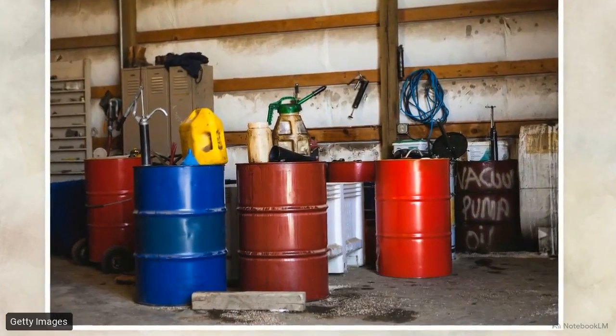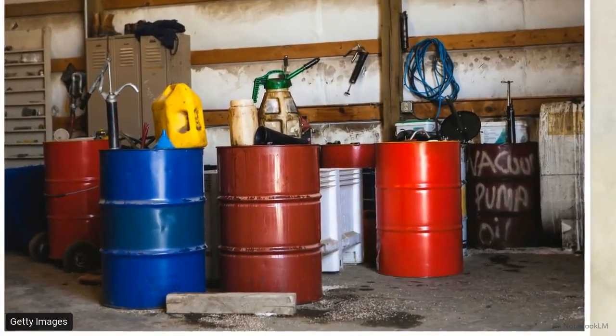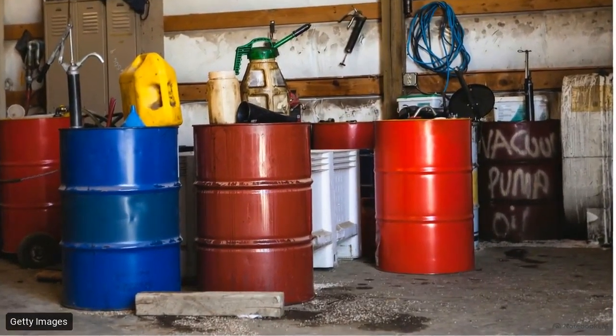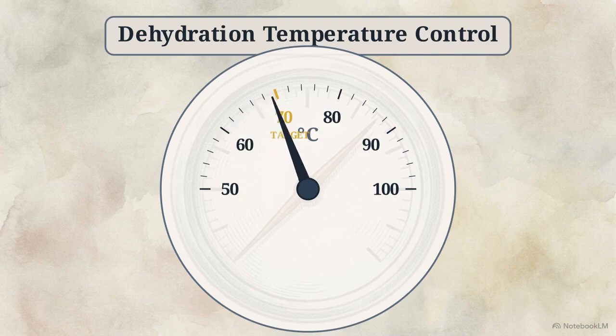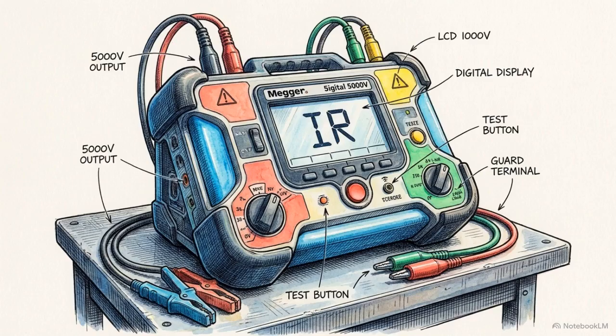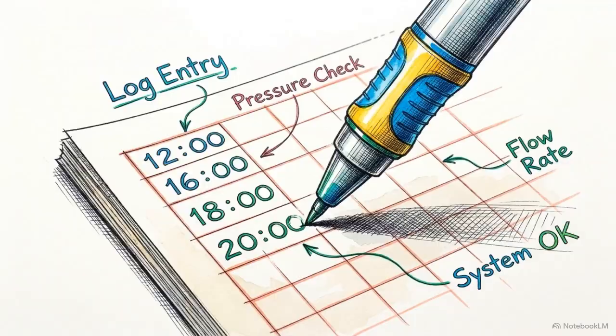Start the filter machine and confirm the vacuum is pulling a minimum of 710 millimeters of mercury. Maintain the oil at 70 degrees Celsius. Do not exceed 80 degrees, or the oil will carbonize and cause a sharp increase in acidity. Track your insulation resistance, or IR, using a 5,000-volt megger. Log your data every 4 hours, then switch to 2-hour intervals once the oil reaches 70 degrees.